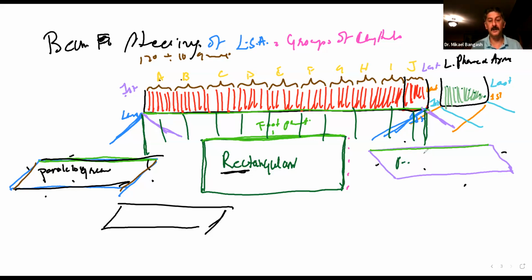But the difference between the two is mainly in this parallelogram, if you say A, that would mean this group of crystals is firing first, followed by B, followed by C, followed by D, followed by E, F, G, H, I, J being the last. Whereas this was a parallelogram too, but if you set your beam to be steered in this direction, now group J crystals will fire first, followed by I, followed by H, followed by G, followed by F, followed by E, followed by D, followed by C.